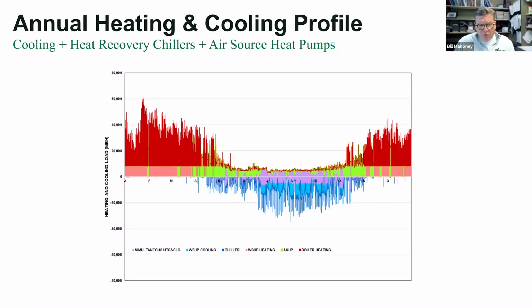So the way this profile breaks down, first you would do simultaneous heating and cooling. That's all the purple in the middle here, and there's not a whole lot of that. But the heat recovery chillers would do our simultaneous heating and cooling. That's our highest COP, 7 or so for that. And then beyond that, in the summertime, if you needed more cooling, then you would use the ground water. It's labeled here as water source heat pump cooling.